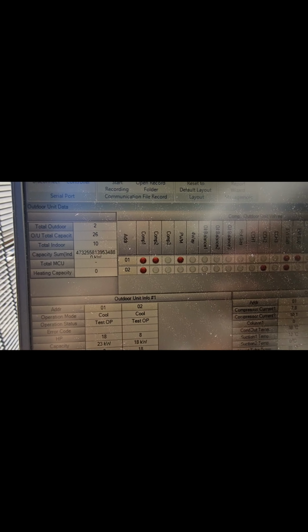Let's just quickly have a look at the outdoor data. I'm still a little bit concerned about that high pressure as well as the low pressure, more specifically our low pressure. High side is almost at target. We're a tad high on the low side. Let's just wait for compressor 2 to kick in as well. Okay, there we go. Compressor 2 on the master condenser just switched on. The master condenser has got 3 compressors and our slave unit has only got 2, so we should see a difference in our pressures. So far discharge temperatures are not looking too crazy.